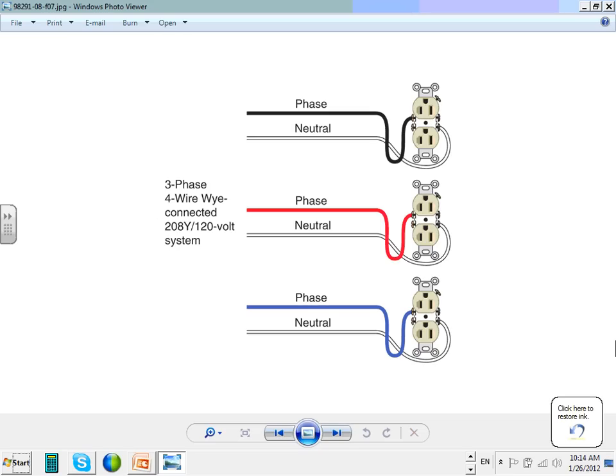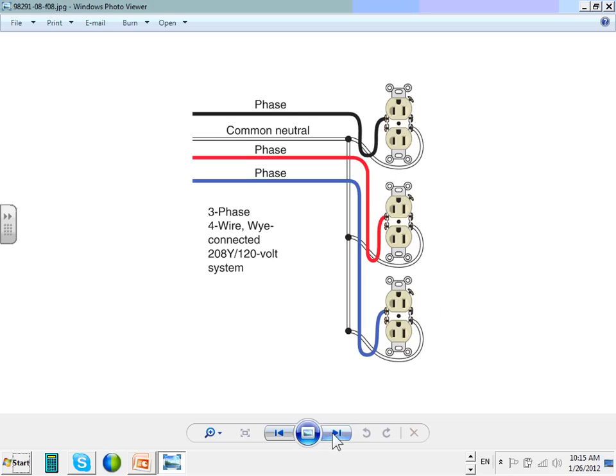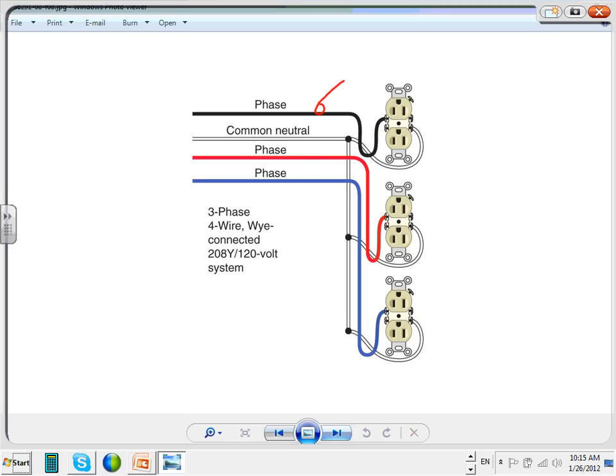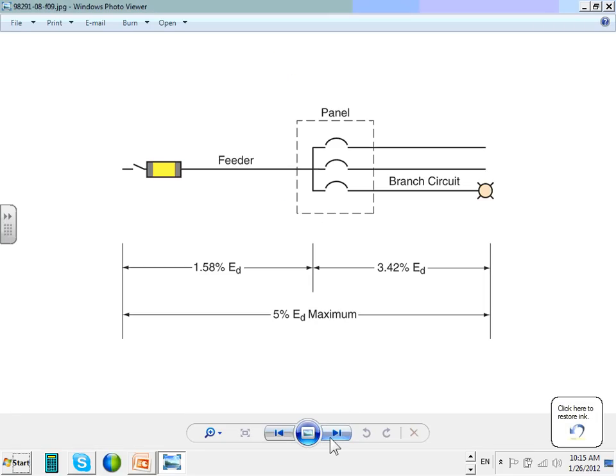The question, how do you solve the problem? A dedicated neutral with every circuit. That will solve the problem, right? That's the most common practice. If you use a common neutral, guys, this is also another practice. This will be number 12. Let's make the neutral number 10. I can pull a number 10 neutral, common. Not commonly used, because now we have to terminate number 10 at the receptacles that might not be rated for number 10. Most likely rated, but the first solution is the best solution. A dedicated neutral with every phase.